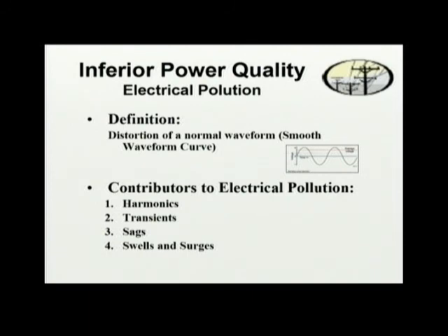Inferior quality power is distortion of the normal 60 Hz waveform and causes pollution of the electric supply. Harmonics are frequencies greater than 60 Hz. Transients are short duration voltage spikes. Sags are voltages 5% less than normal or nominal. Swells are voltages 5% more than normal, and surges are short-term high-voltage transients. They all contribute to electrical pollution of the environment. Frequencies other than 60 Hz are called electrical noise.